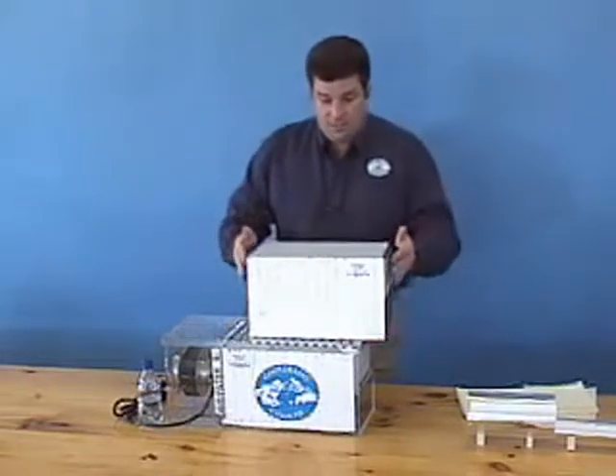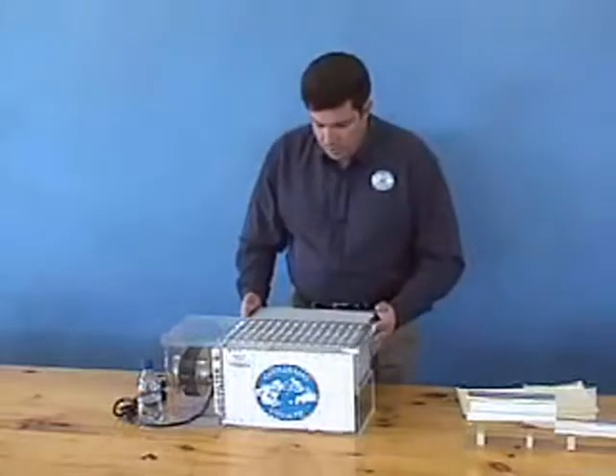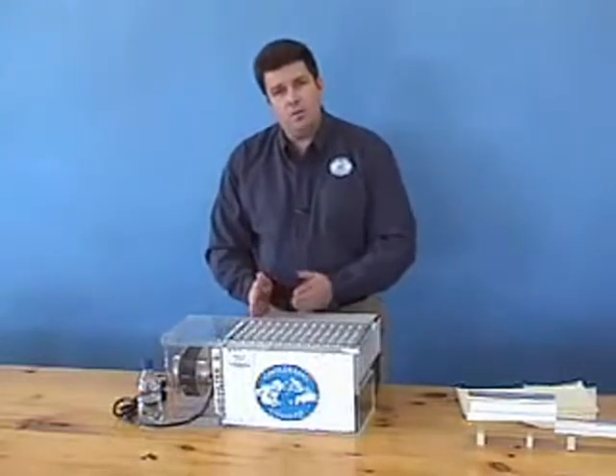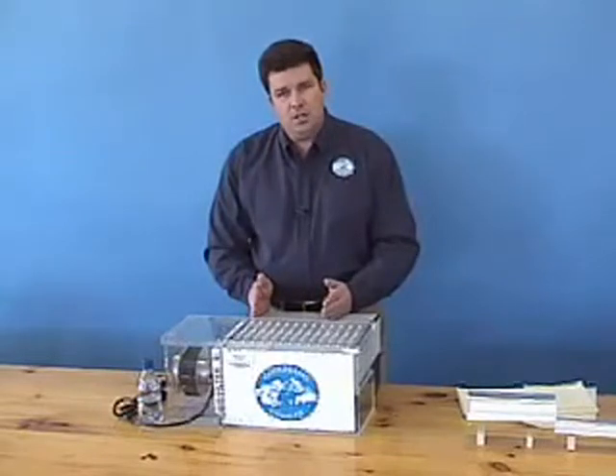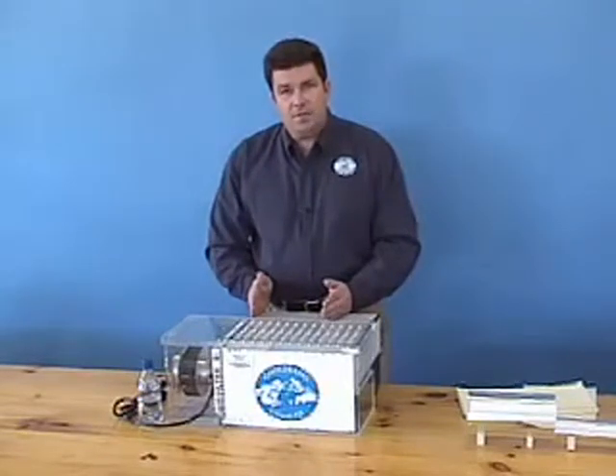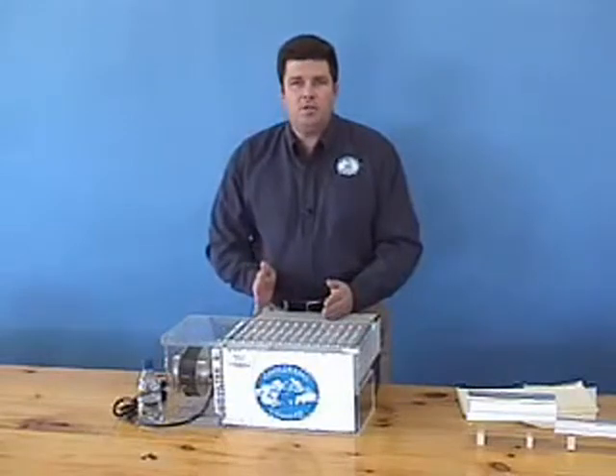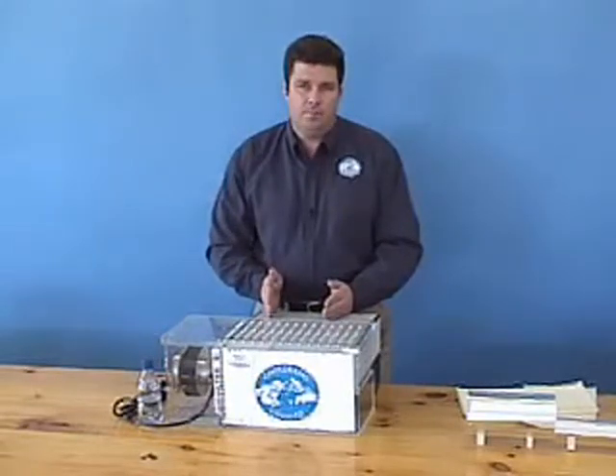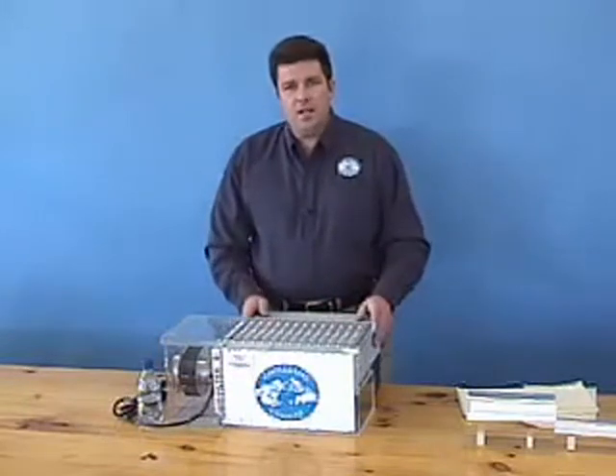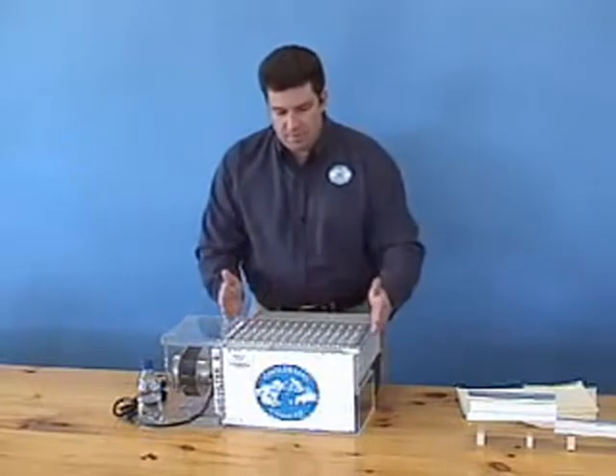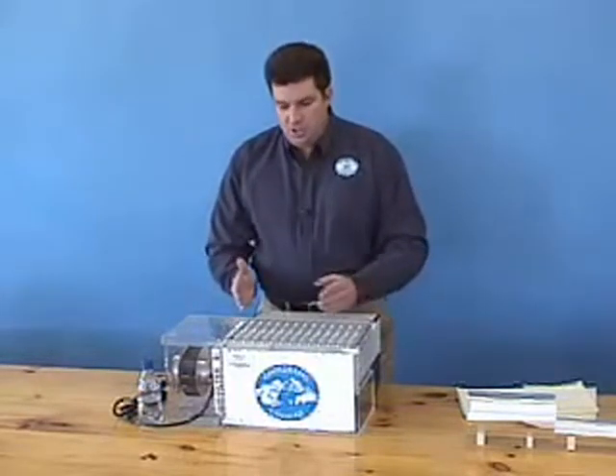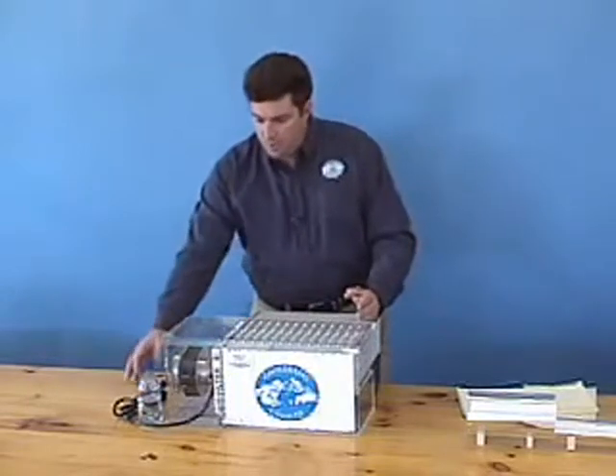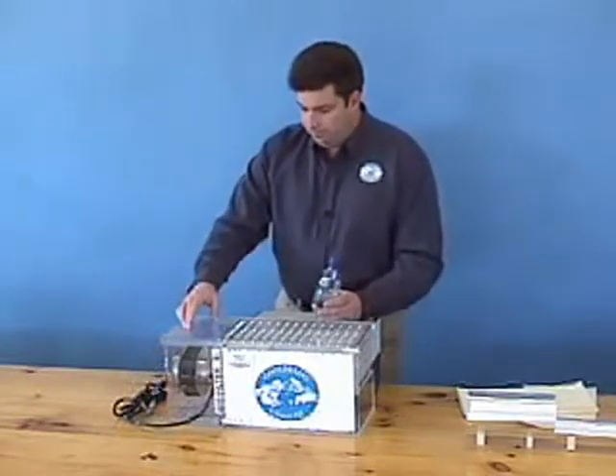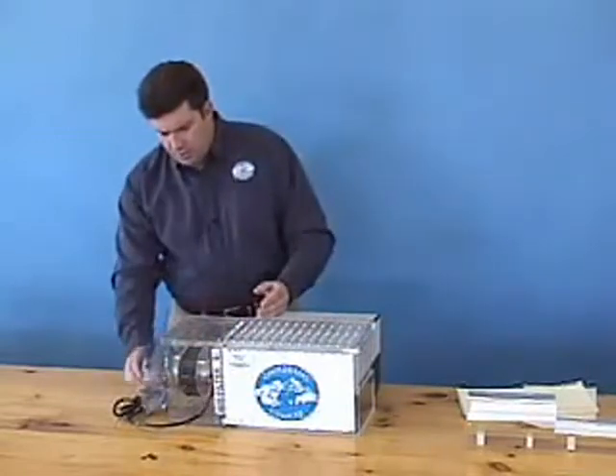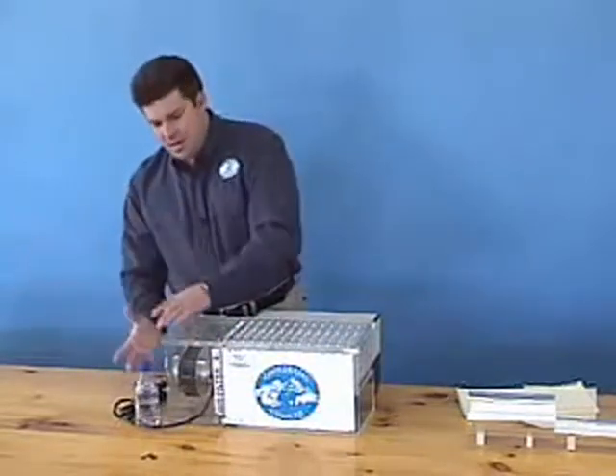This is the heart of the Maisotsenko cycle, incrementally cooling both the product and working air streams through heat exchange while incrementally fractioning off some air to aid in lower temperature vaporization and mass transfer. In short, this elegantly ingenious and simple process is how we achieve temperature drops that have never been seen before. This huge temperature drop is created with a little water and the power of a fan. In fact, if you could harness the wind through this little machine, you would not need any power at all.